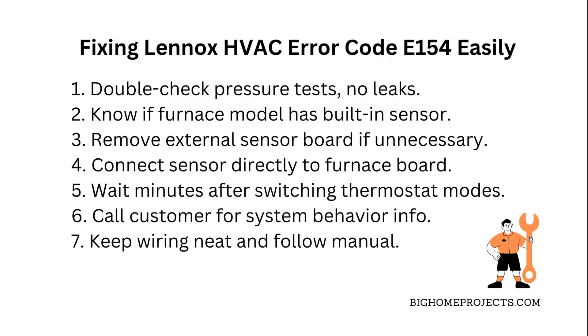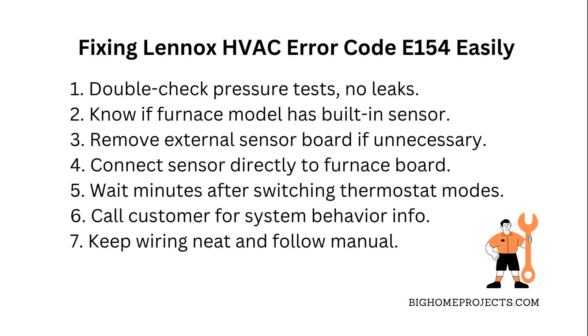Make sure there are no leaks before moving forward. If you see that E154 code pop up on the circuit board, it usually means there's an issue with the refrigerant leak sensor wiring or setup.